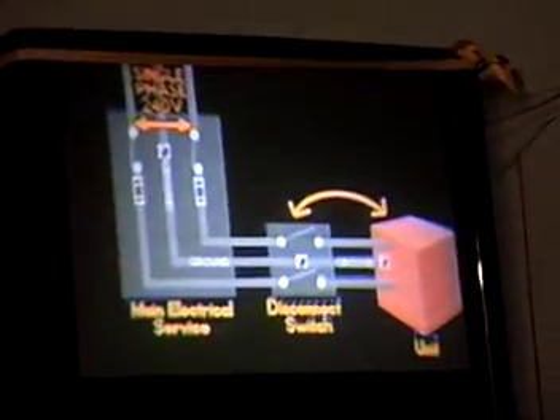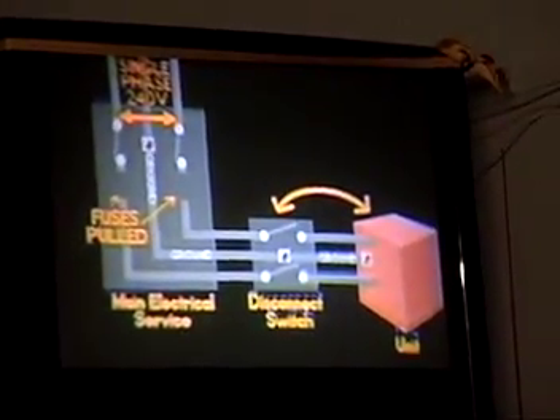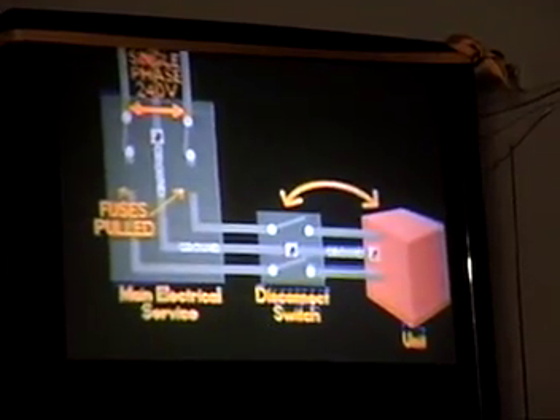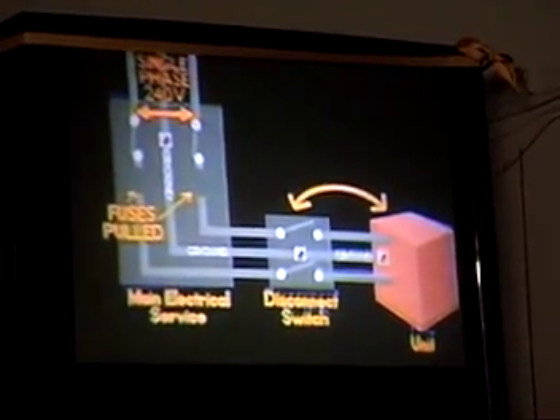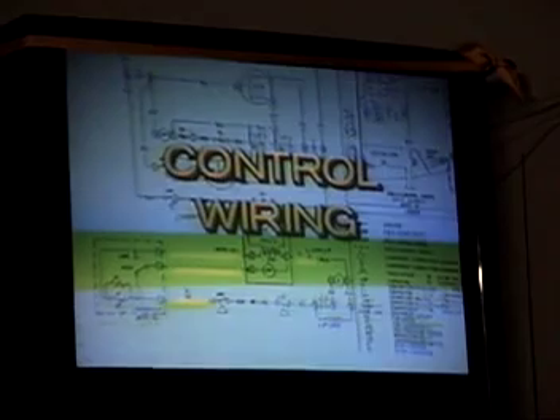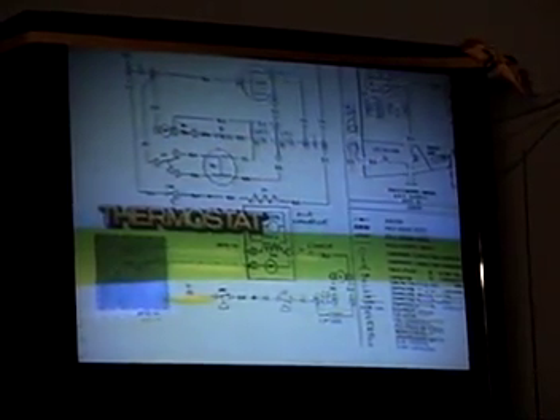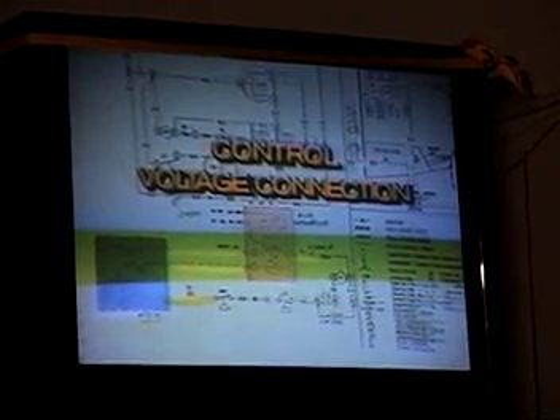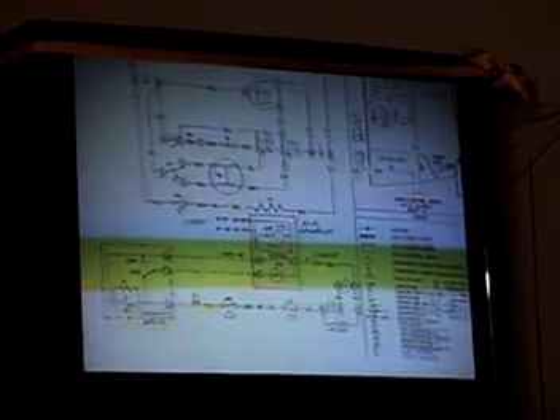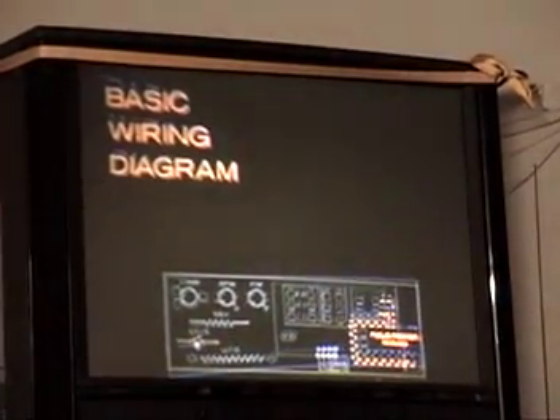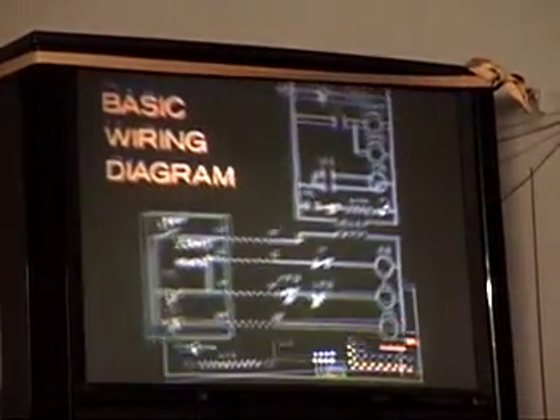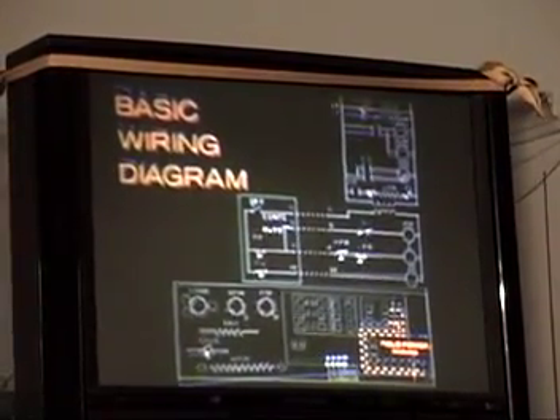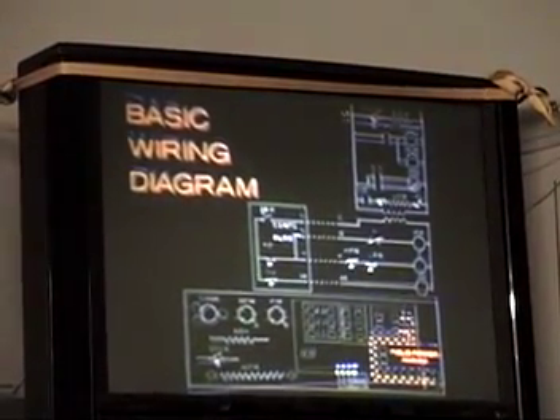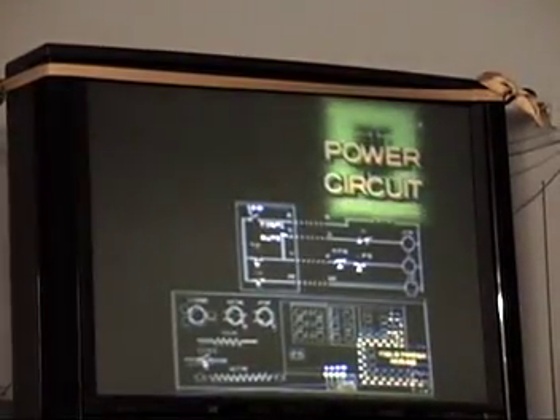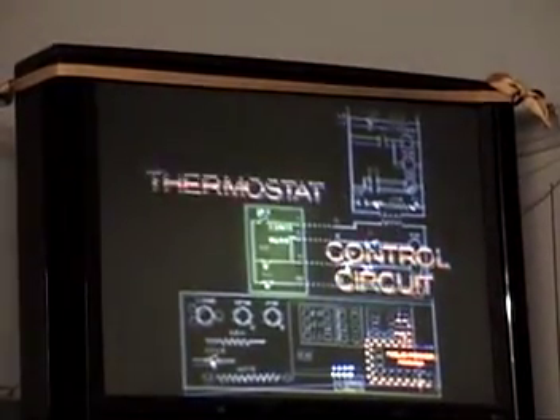The power must be shut off at the circuit breakers or fuses and at the disconnect switch to the unit when work is being performed. Control wiring will be run from a remote thermostat to the control voltage connections in the unit. It would be impossible to construct, install, or service a heating or cooling system without the aid of a wiring diagram. In this program, we'll learn about the functions of the components and the interaction between the power circuit, the control circuit, and the thermostat.